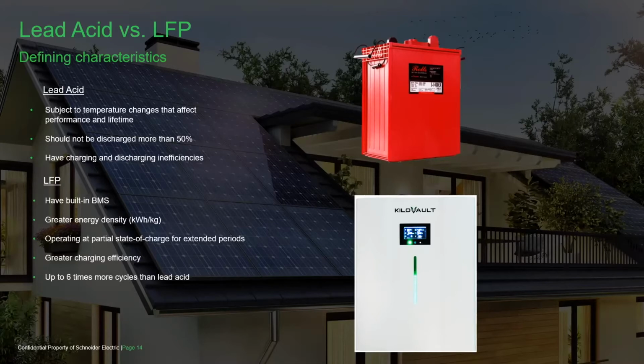Lead acid batteries typically don't like to be discharged more than 50%, which is why sulfation occurs. Some lead acid batteries advertise carbon coating and different treatments that allow a deeper depth of discharge, but as a general rule, 50% is the limit. If you go beyond that, you're cutting into the life of the battery, or you'll have to equalize them more. You also have charging and discharging inefficiencies, and they're not as efficient as a lithium iron phosphate battery.